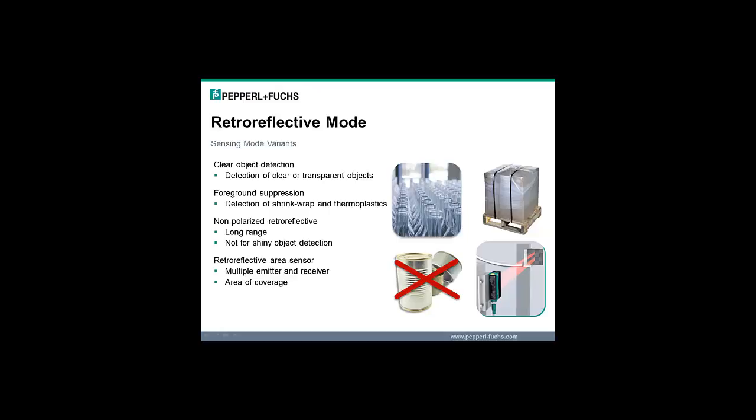Retroreflective mode sensors also have several special variations. These include clear object detection sensors which reliably detect clear or transparent objects, foreground suppression sensors that reliably detect shrink-wrapped pallets and some thermoplastics, non-polarized retroreflective sensors which have higher detection ranges compared to polarized retroreflective sensors but are not recommended for shiny object detection, and retroreflective area sensors which have multiple emitter and receiver elements that provide an area of coverage.